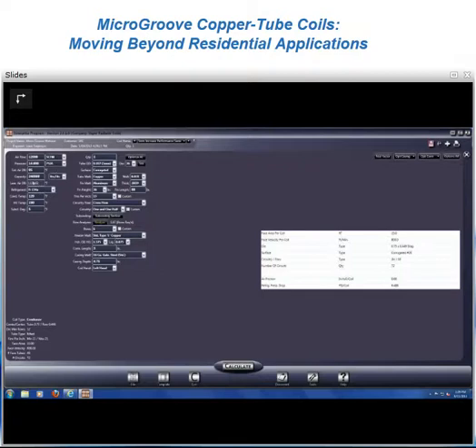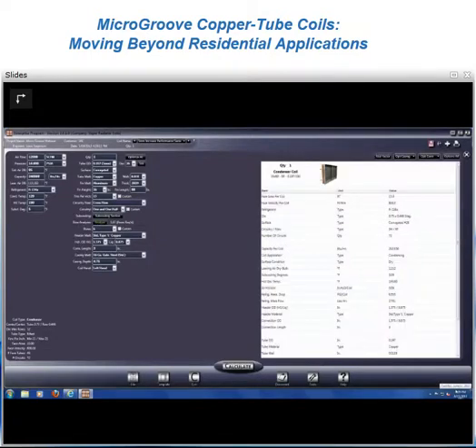What I've done now, however, the big difference is this. My target is to get more performance, so I'm increasing my BTU required from 198,000 up to 240,000. Same physical space. And to do that, there's a lot of ways you could do it, but the way we're going to do it for this analysis is increase the airflow to 12,000 CFM while keeping the air friction the same. Big thing we want to look at there is I don't want to put more air friction in the system. So let's just take a quick look. We'll analyze our 6-row coil here, calculate that out, and let's just jump over to the schedule. We'll show you all 4 coils together here.